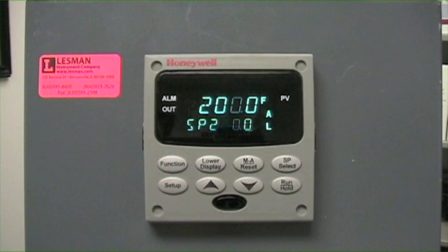Also, you should be aware that Accutune drives the output of the controller to 100% full on, then to 0% full off, back to 100% full on, and then to 0% full off in order to watch the response of the process. The implication of this is that your process can see or be exposed to 100% output or 0% output for some period of time. If your process or its contents can be damaged by not maintaining a tight window, then Accutune might not be the appropriate thing to use unless you can somehow simulate a dummy load.